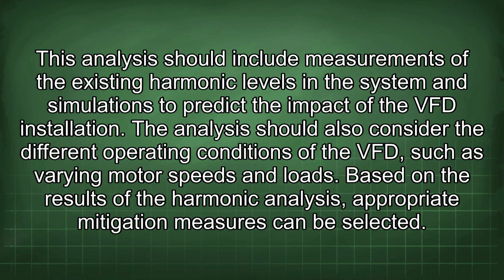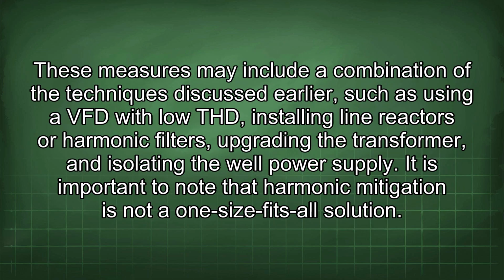This analysis should include measurements of the existing harmonic levels in the system and simulations to predict the impact of the VFD installation. The analysis should also consider the different operating conditions of the VFD, such as varying motor speeds and loads. Based on the results of the harmonic analysis, appropriate mitigation measures can be selected. These measures may include a combination of the techniques discussed earlier, such as using a VFD with low THD, installing line reactors or harmonic filters, upgrading the transformer, and isolating the well power supply.